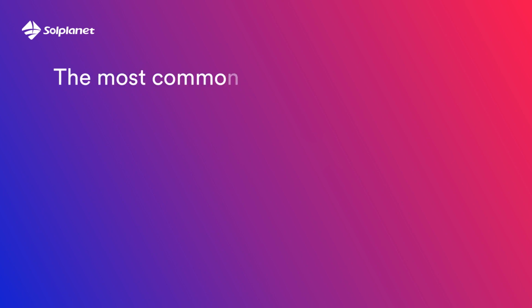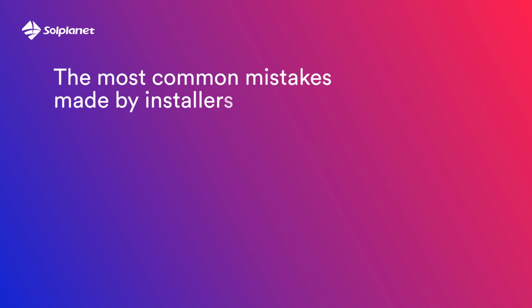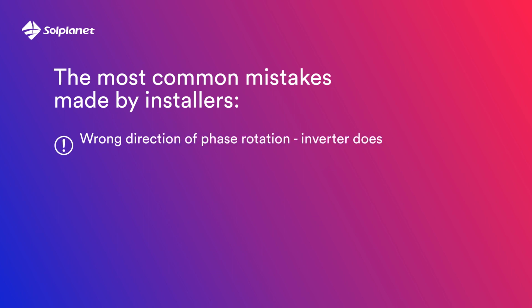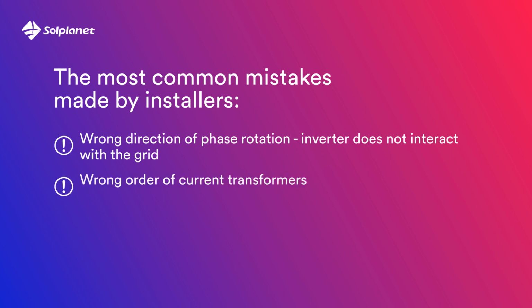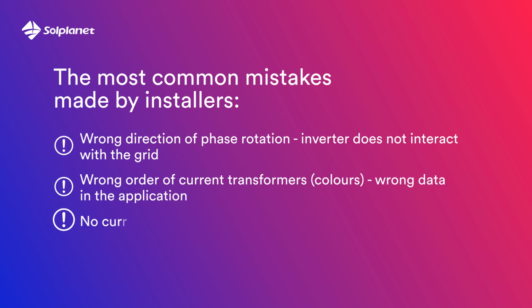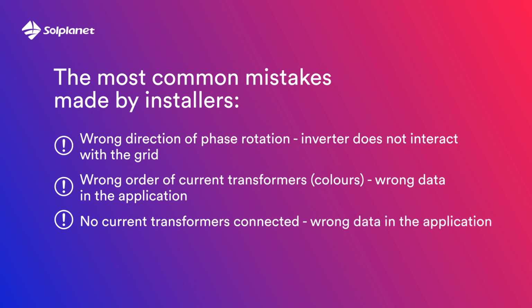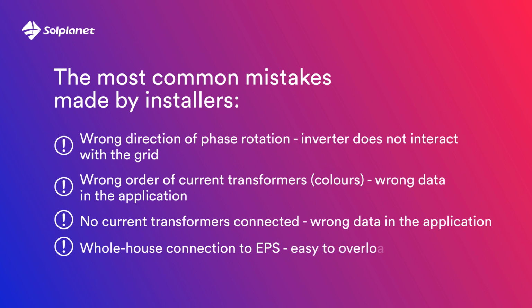The most common mistakes made by installers. Wrong direction of phase rotation: the inverter is not working with the grid. Wrong order of current transformers colors: incorrect data in the application. No current transformers connected: incorrect data in the application. Connecting the whole house to the backup: it's easy to overload.